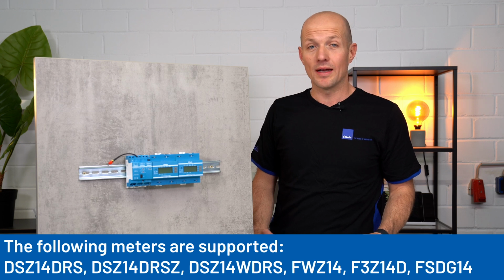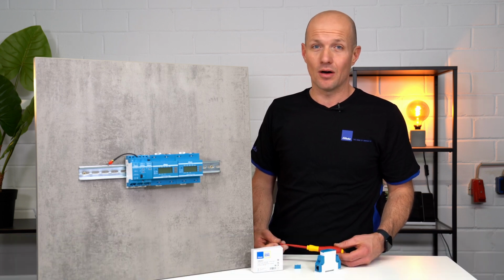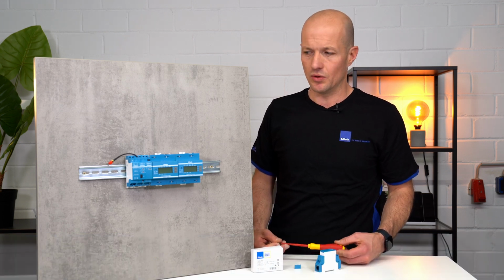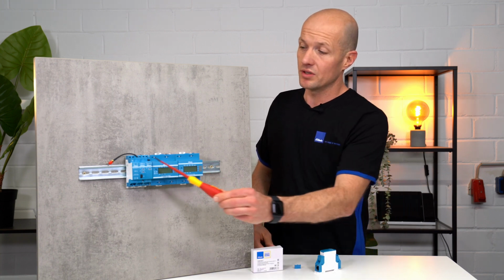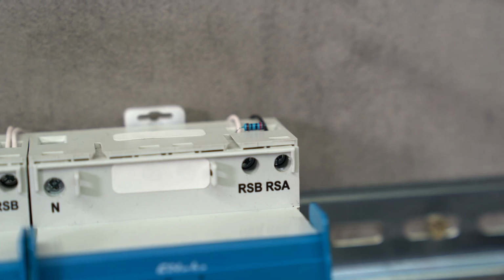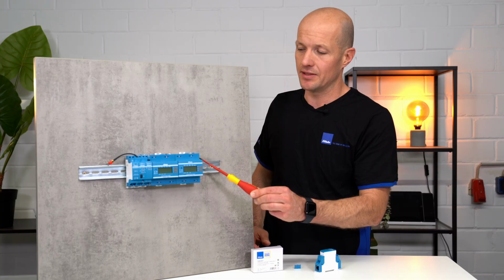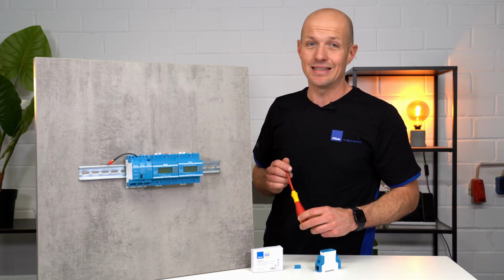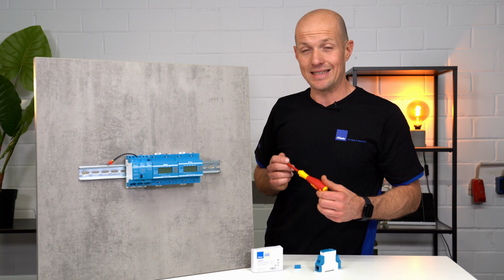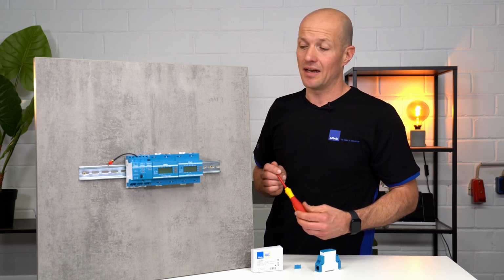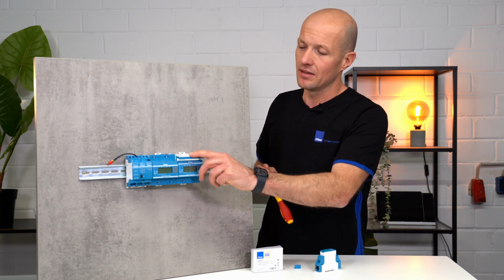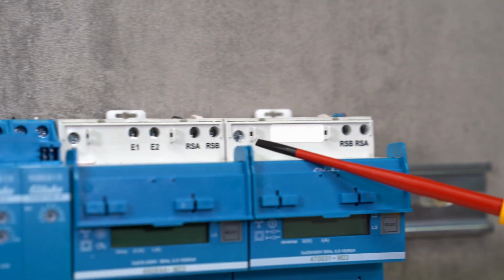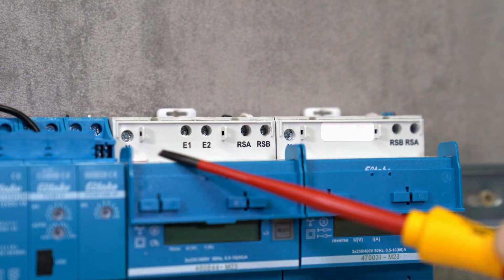When setting up the Series 14, please ensure that the bus line is wired correctly. It is important that you terminate the bus at the beginning and end with a terminating resistor. It is also important that you connect the RSA and RSB bus lines correctly. Depending on the device, please ensure that the wiring and assignment of the individual connection terminals is correct.